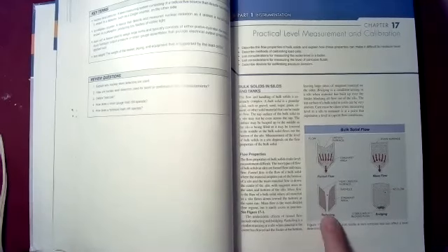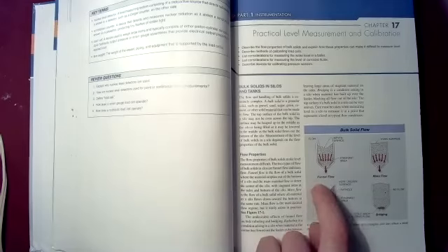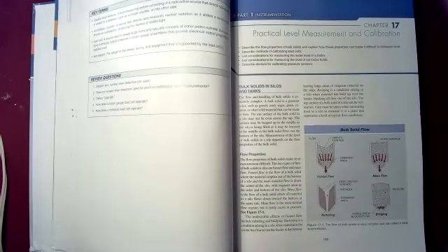For instance, if you have a rat holing, where you put your sensor matters a lot. If I have a sensor in the direct middle of this silo looking down, it's going to look like that silo is empty. If I have a sensor here right on the left-hand side, then it's going to look like that silo is nearly full. The only way I can accurately understand how much quantity I have in that silo is by weighing the silo using my weight measurement system.